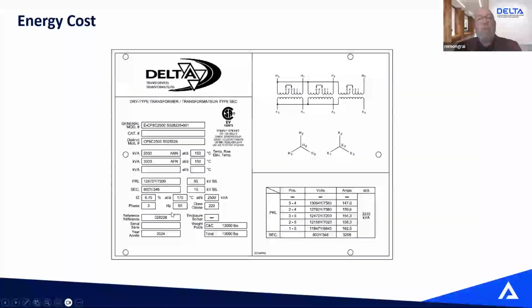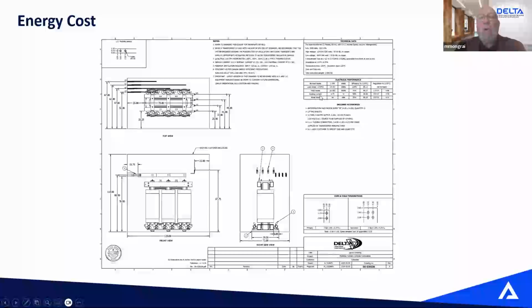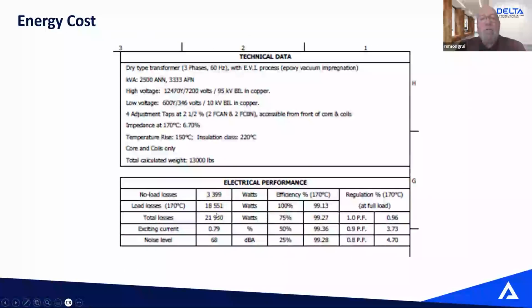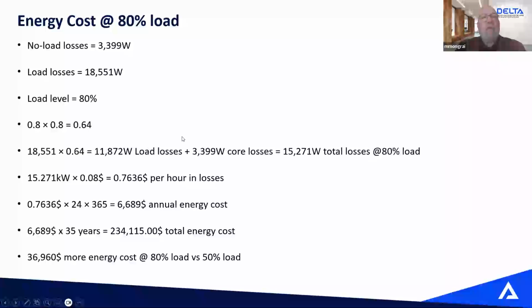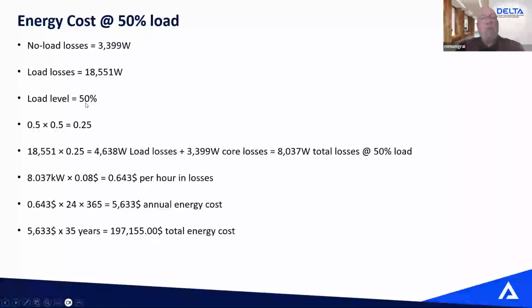To give you an idea, if you want to do some rough calculation, this is a typical example, a Delta 2500 kVA that we built a few years ago. On our drawings at Delta, we're generous. In that box here, you have your losses: no load losses, full load losses, total losses. From there, you can run the same kind of maths. Let's say you have a load level of 50%, so 0.5 times 0.5 equals 0.25, 25% of your load losses. So you multiply your load losses by your load factor, plus your no load losses, and that gives you 8 kilowatts of losses. Same maths with the same amount. So I'm at $5,600 a year of cost of energy, and over the lifetime, I'm at 197K.